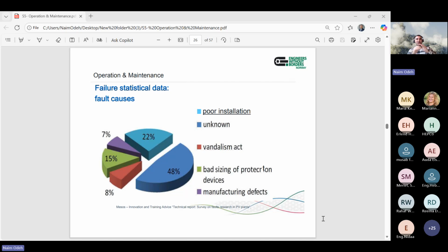After maybe five years, if you go there, you find most of them not there. Maybe one solar module was not matching with the rest of the system. It was installed there, and after some time it causes a problem, so they cannot find that this module is different from others. Maybe the shape is exactly the same, but the parameters are not. This is something you find at the time of the first visual inspection after the project is installed. Sometimes, when you have the same party doing the design and installation, or installation and operation and maintenance, people hesitate to report that their installation team did something wrong and it should happen in a different way. So they don't report this stuff, and the problems build up over time and become difficult to solve.